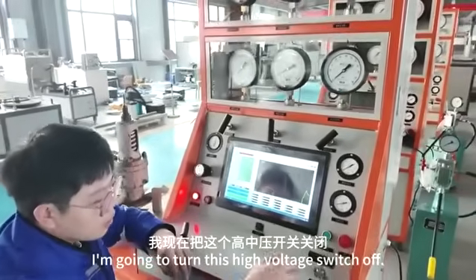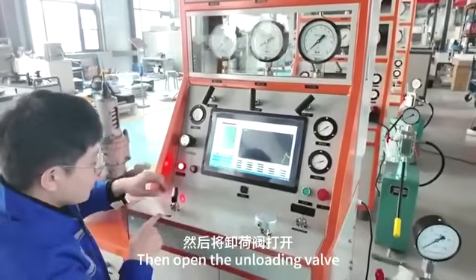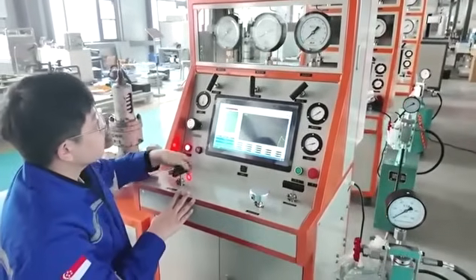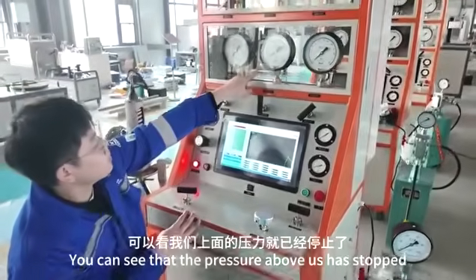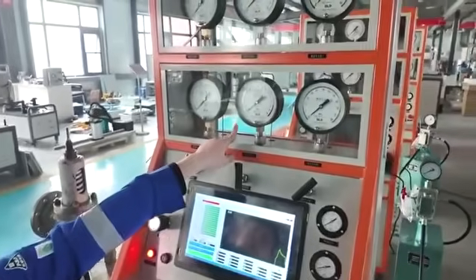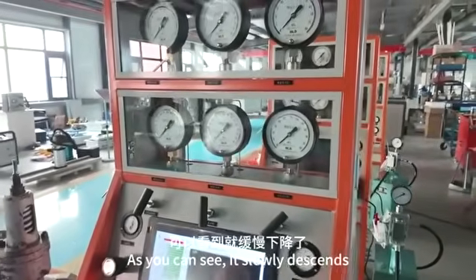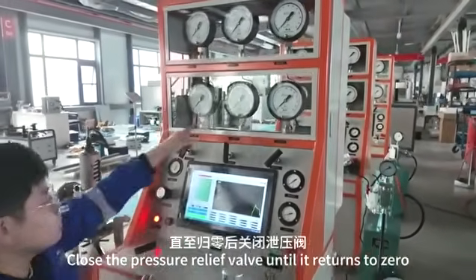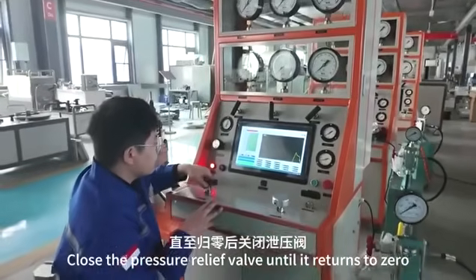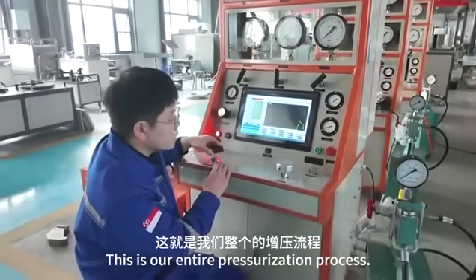I'm going to turn this high voltage switch off. Then open the unloading valve. You can see that the pressure above has stopped rising. As you can see, it slowly descends. Close the pressure relief valve once it returns to zero. This is our entire pressurization process.